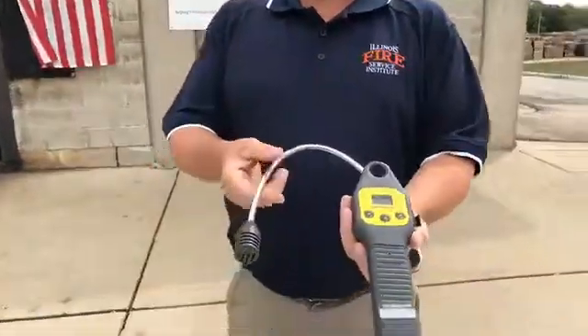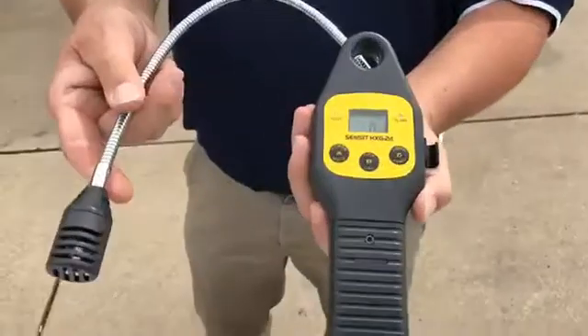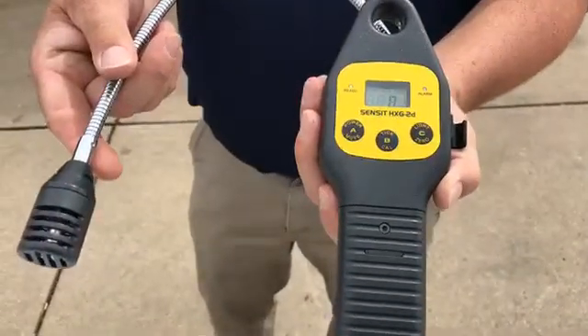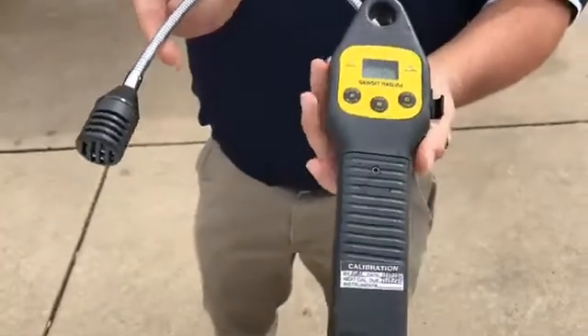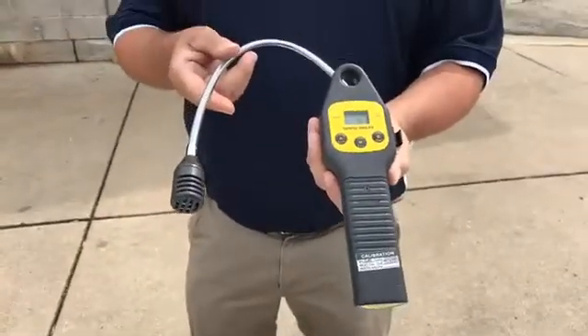First instrument that we're going to look at is the Sensit HXG2D leak detector. Okay, this monitor reads in both parts per million as well as a percent. Actually, at 999 parts per million, as it increases, it's going to automatically convert into a percentage. So it does that for you. It's a nice feature of the monitor. It also has an auto zero function, so that fresh air that we talked about, the instrument will do it on its own, which is a nice feature.